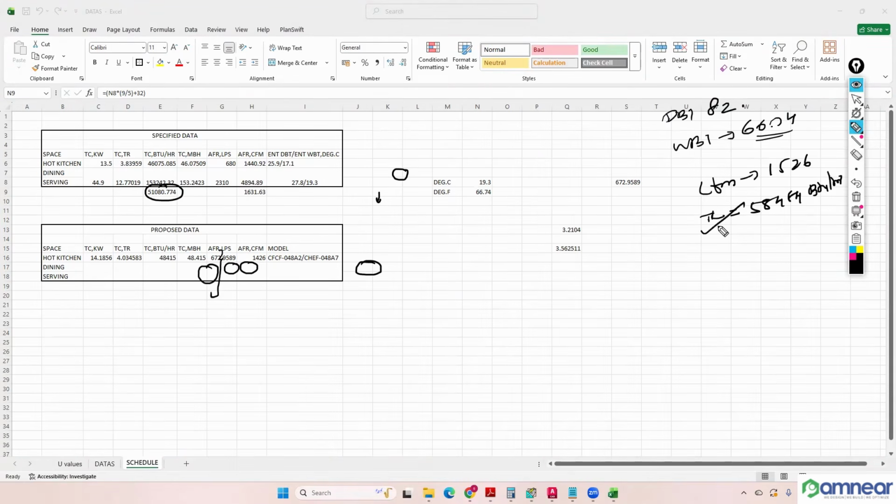That is fine. Slightly the capacity is more, no problem. Even if sometimes the ambient temperature is higher than 46, we are safe. But exactly near 51 we are getting, that is fine. But there is no other option. We can select this one.